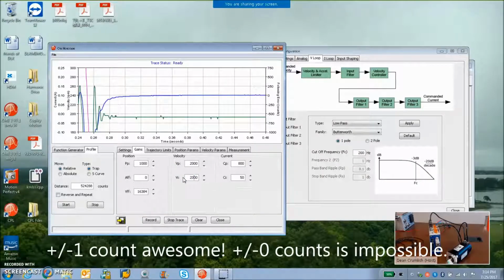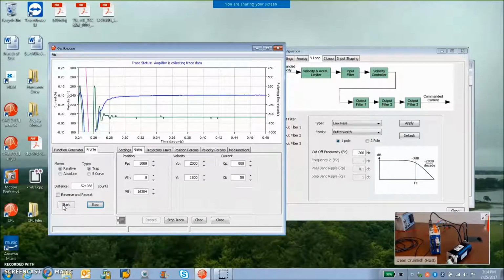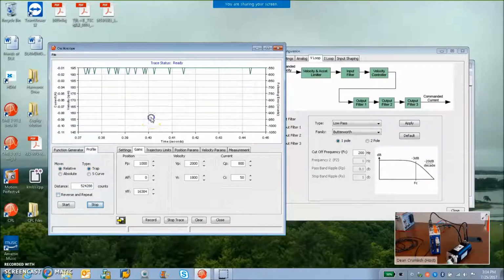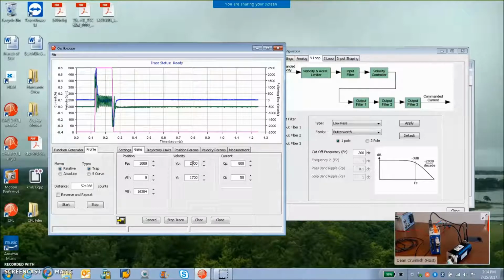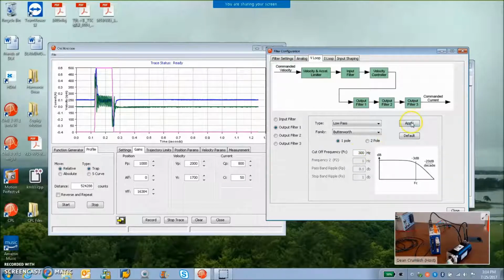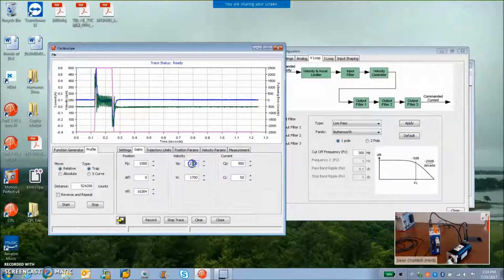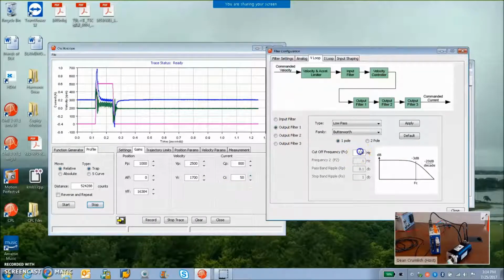And as I don't have inertia, I can get some wicked good tuning here. But the goal with the large inertia still is to get sufficient settling and maximum stiffness in your velocity loop. And again, you know, if the VP value is too high, we'll break into oscillations. But sometimes we can move the pole out a little bit and start to get a little bit more gain in the velocity loop without breaking into oscillation. So some systems don't have mechanical resonances until you get further out.